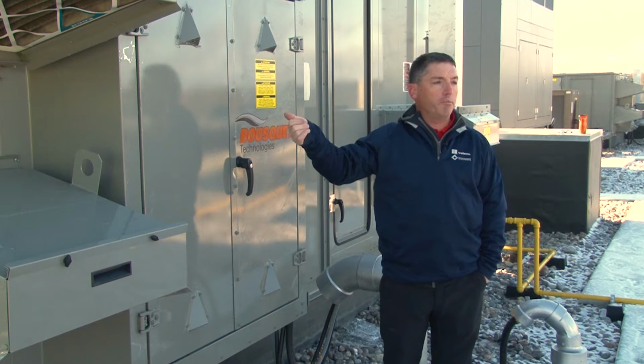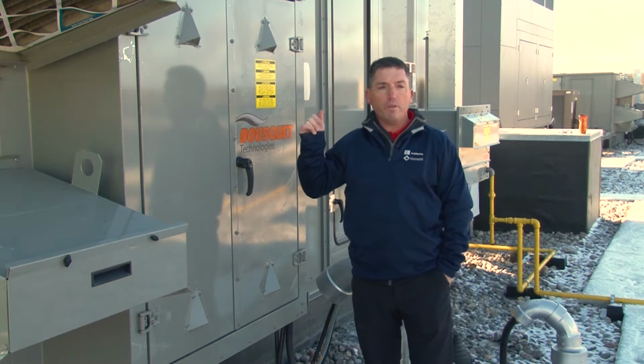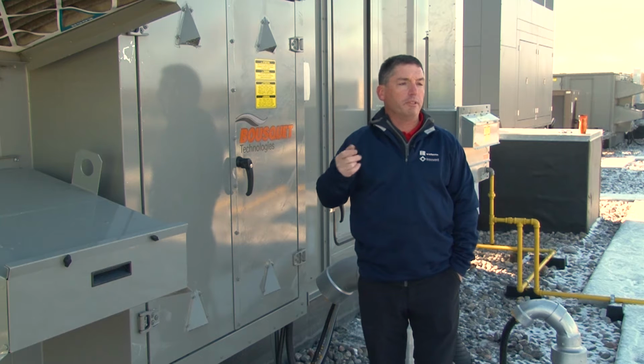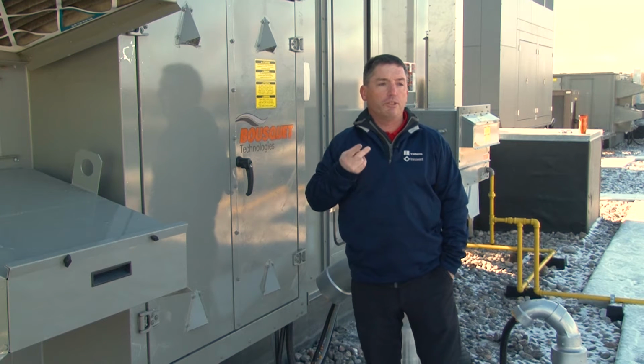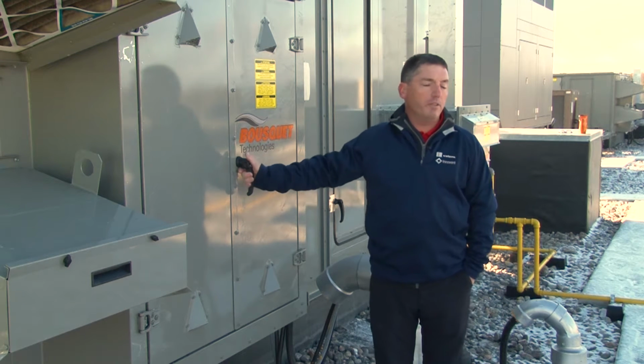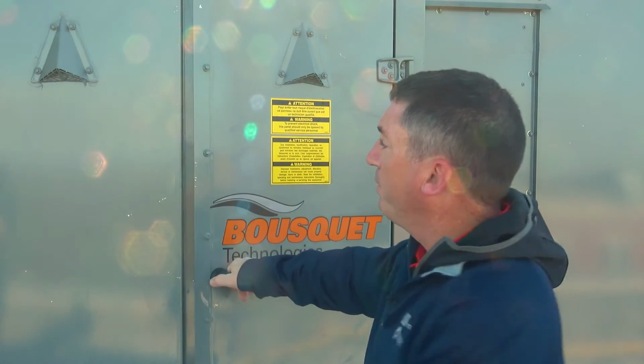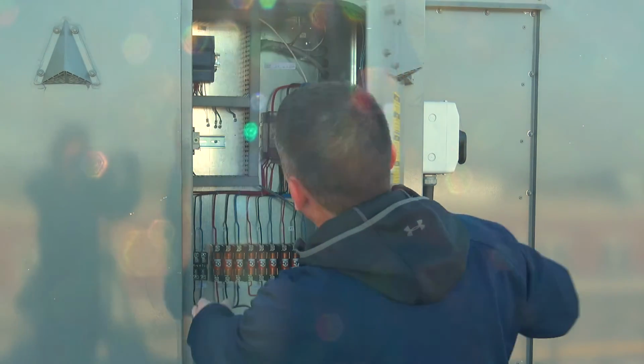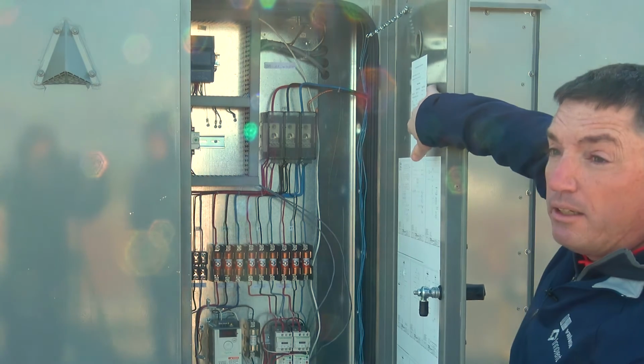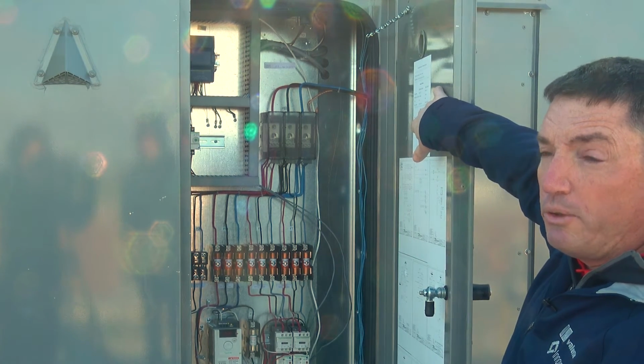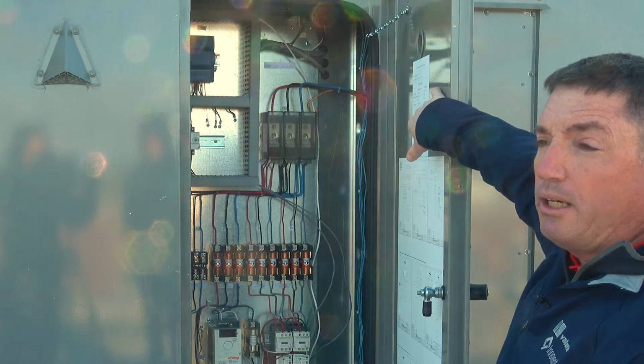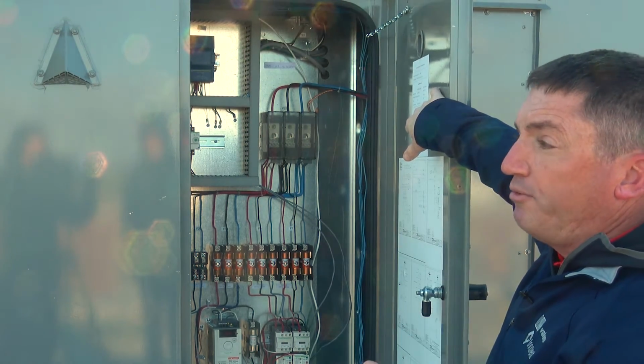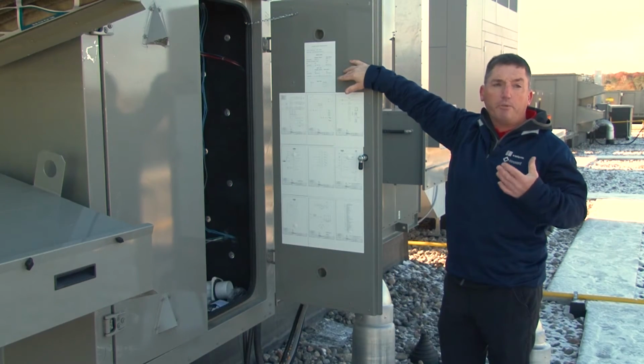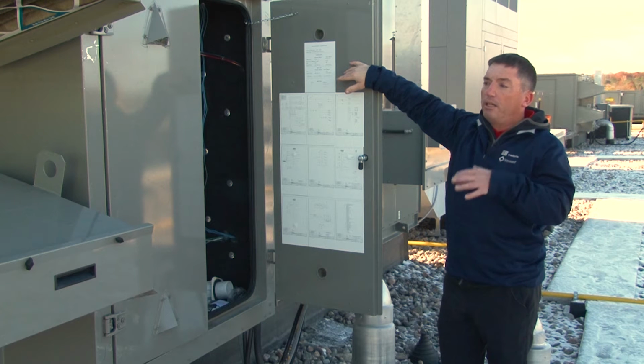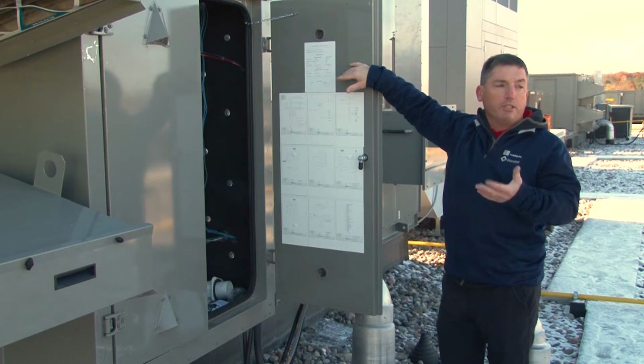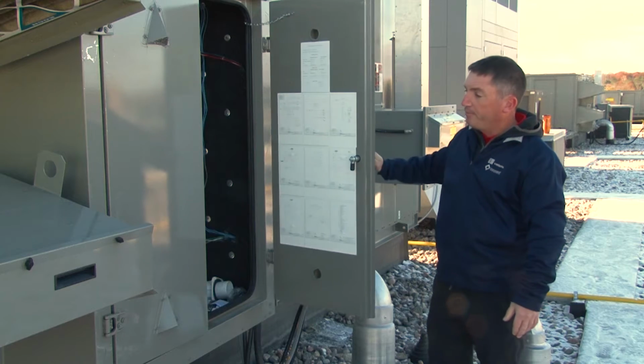The supply blower and exhaust blower are also belt driven. So another maintenance item is the 2 drive belts. All of the maintenance information for the belts and the filters can be found on the nameplate just inside the door here. We'll also give you a list that summarizes the 4 units, what size belt, what size filters, quantities, etc. That way you have a general summary all in one location.